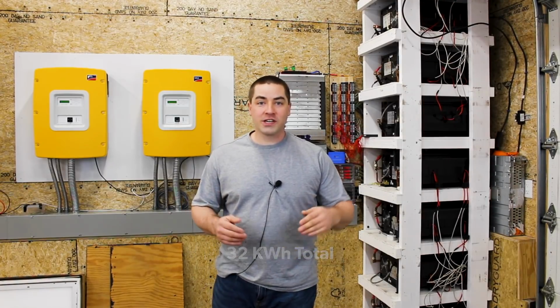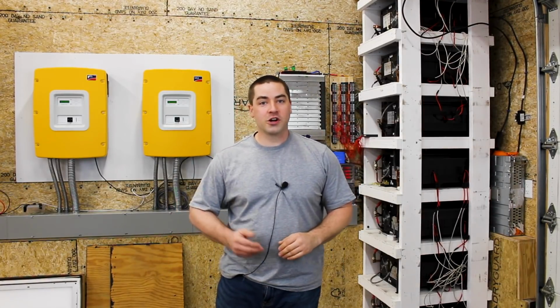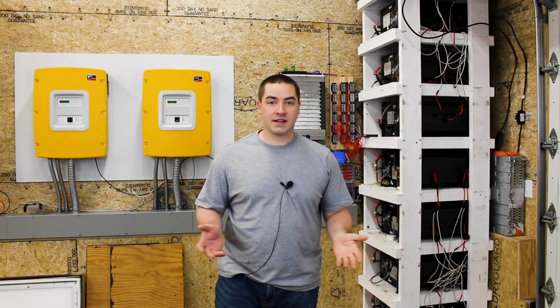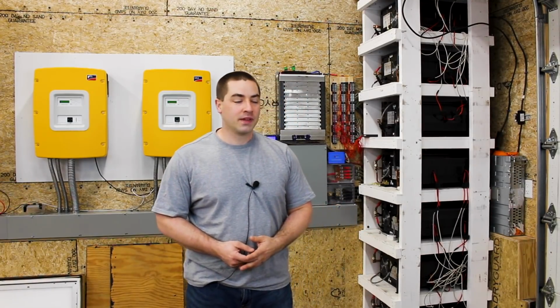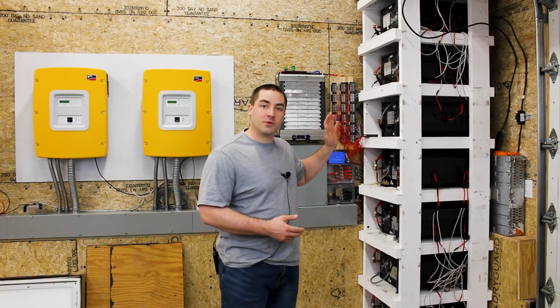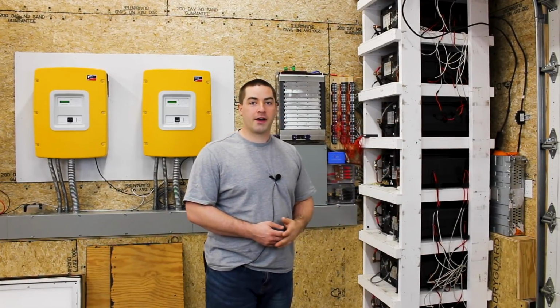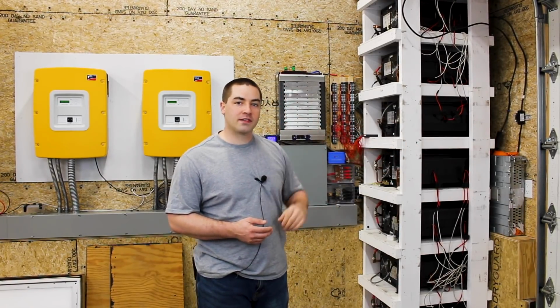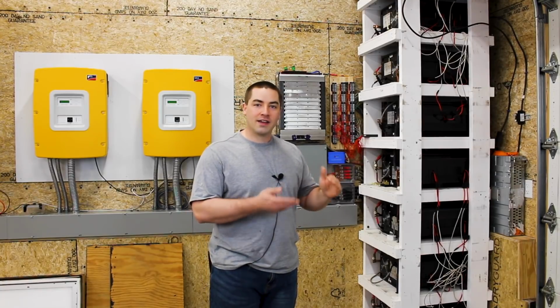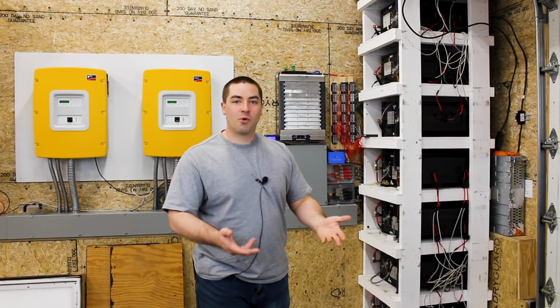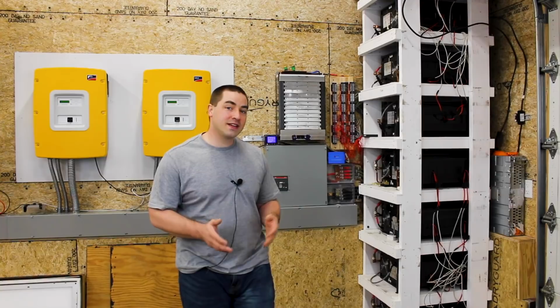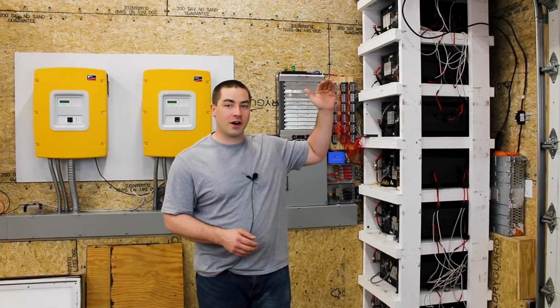However, we're not charging it up to 100% or discharging it to 0% state of charge on every cycle. Part of that is because I want to extend the life of the battery, and if you stay away from the top end and the bottom end in your cycling, you'll get more total cycles.